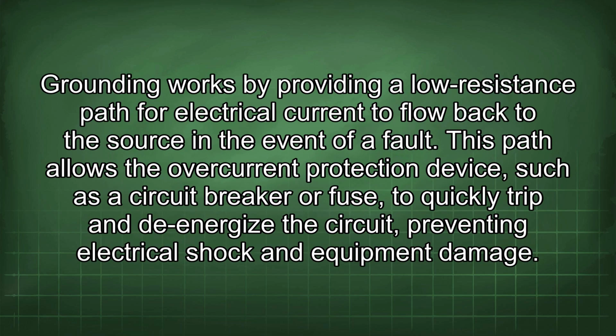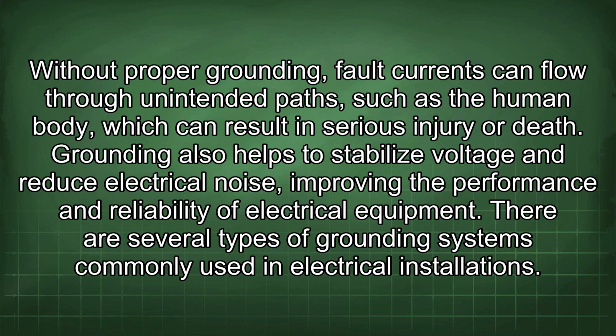Grounding works by providing a low resistance path for electrical current to flow back to the source in the event of a fault. This path allows the overcurrent protection device, such as a circuit breaker or fuse, to quickly trip and de-energize the circuit, preventing electrical shock and equipment damage. Without proper grounding, fault currents can flow through unintended paths such as the human body, which can result in serious injury or death. Grounding also helps to stabilize voltage and reduce electrical noise, improving the performance and reliability of electrical equipment.